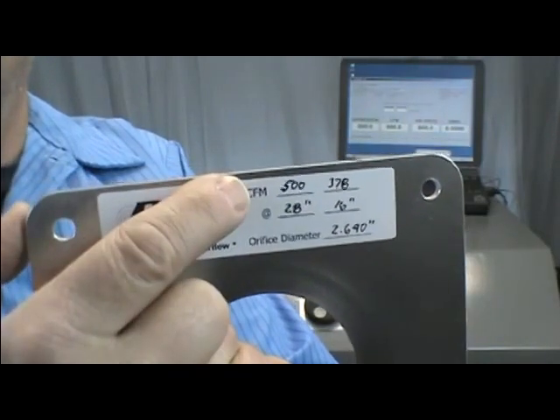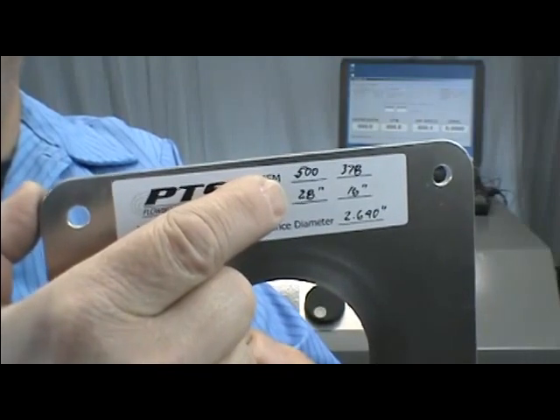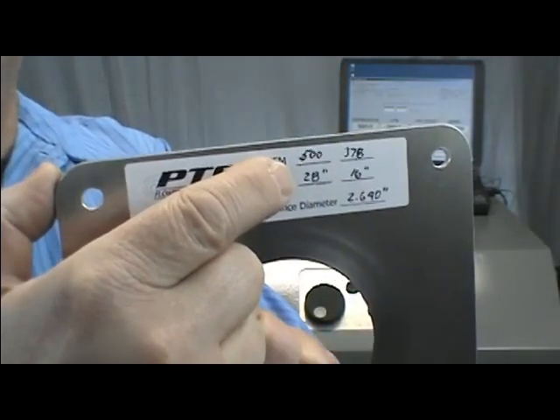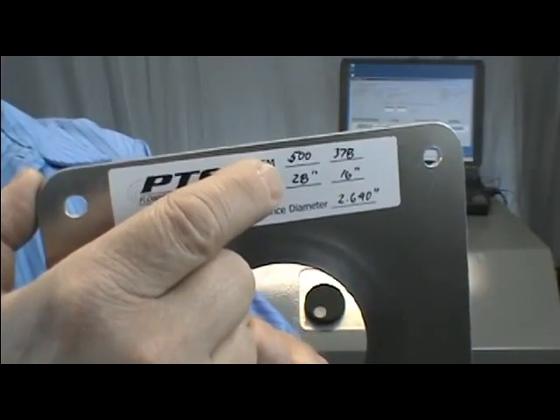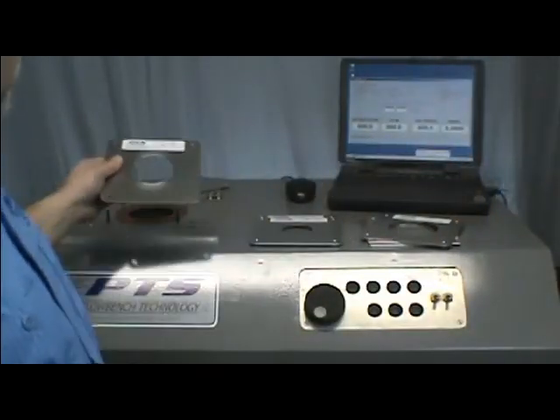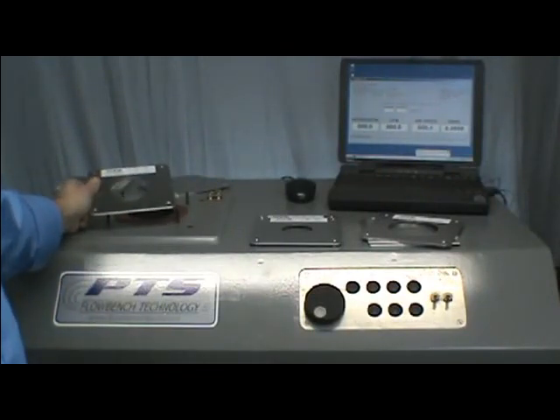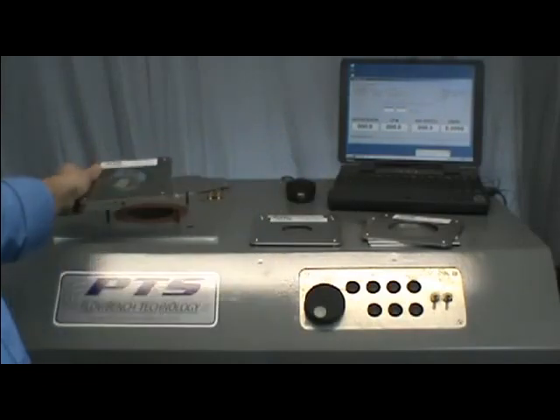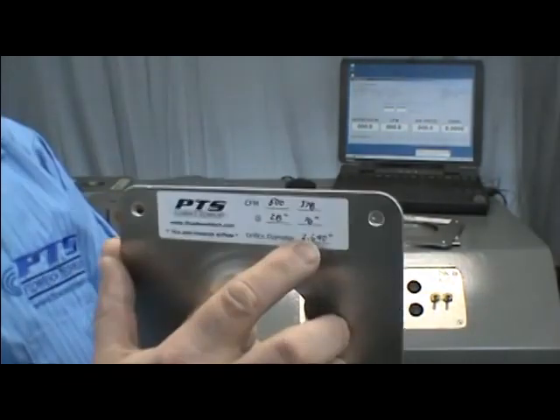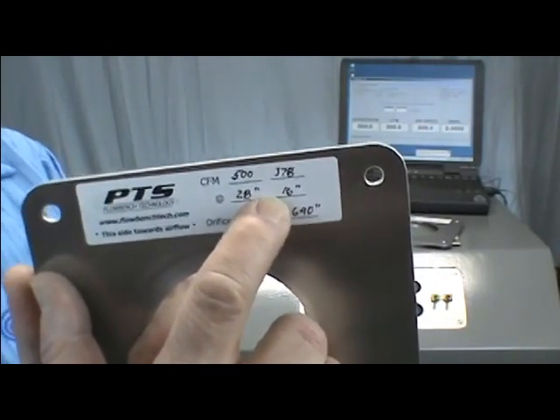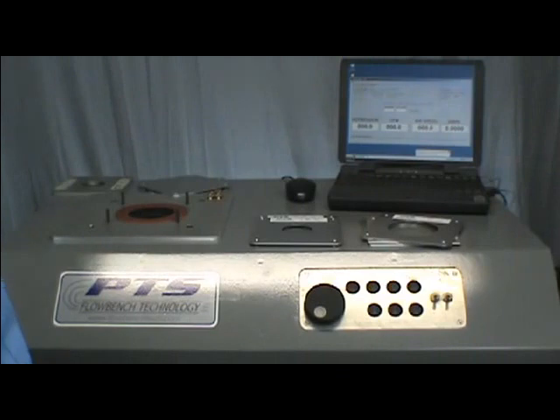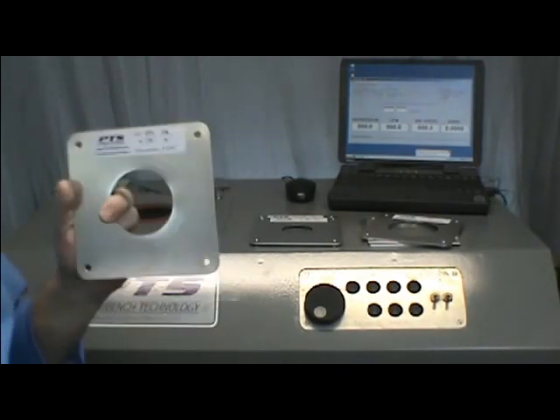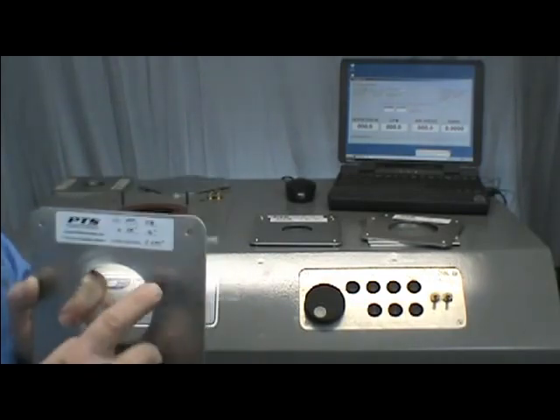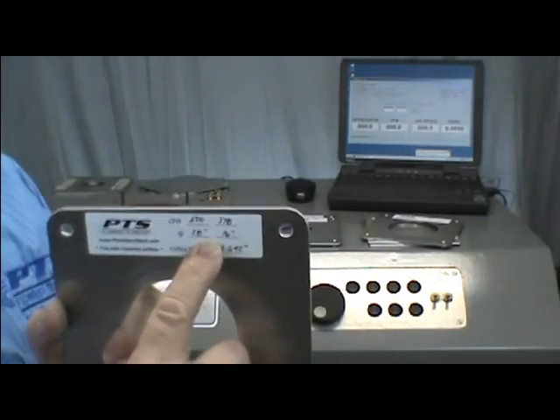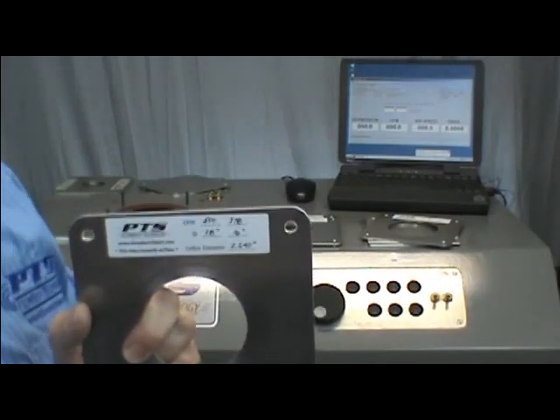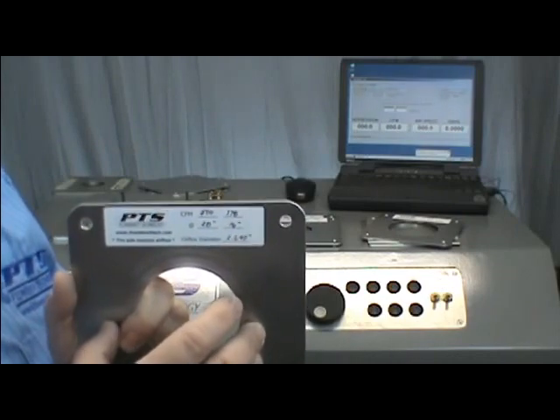The difference between these two is the number on the left at 28 inches is your calibration flow at that given depression when the plate is on top of your flow bench. Keep this in mind. That number is when it's on top of the flow bench. The other number at 16 inches, more than likely, is when the plate is inside your flow bench being used as a measuring orifice. Okay, the differential pressure is 16 inches from the top chamber to the bottom chamber, and you're measuring that flow across the plate.